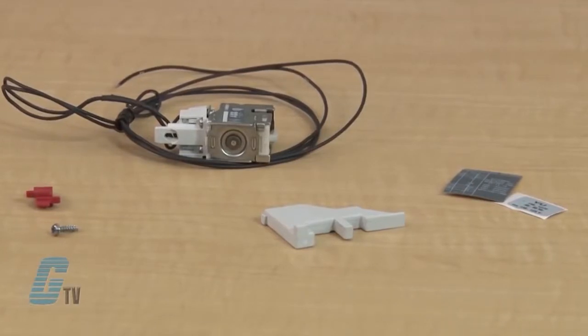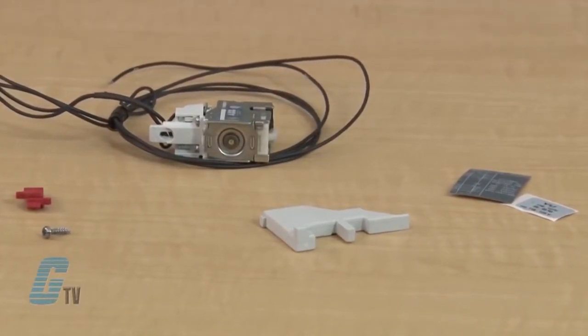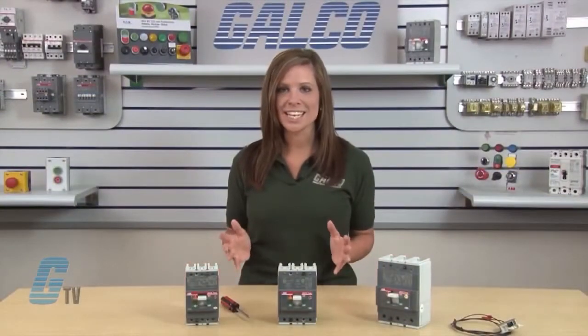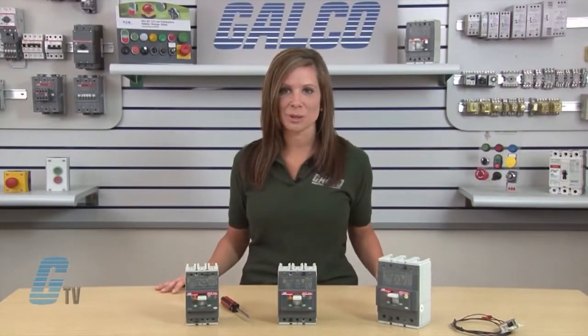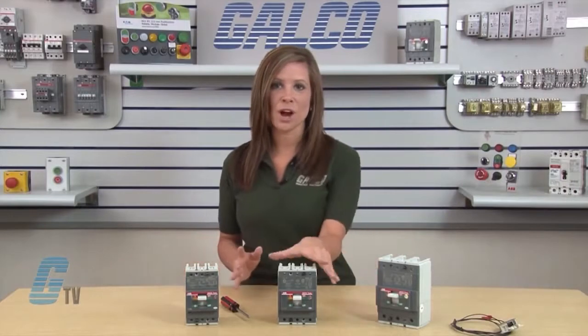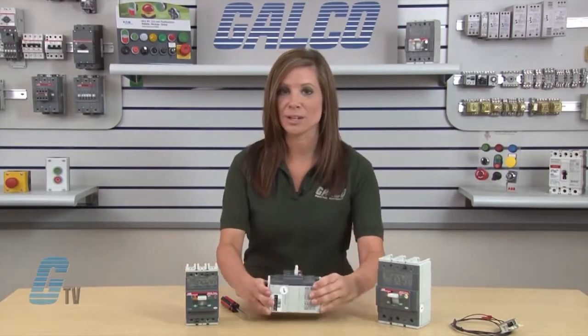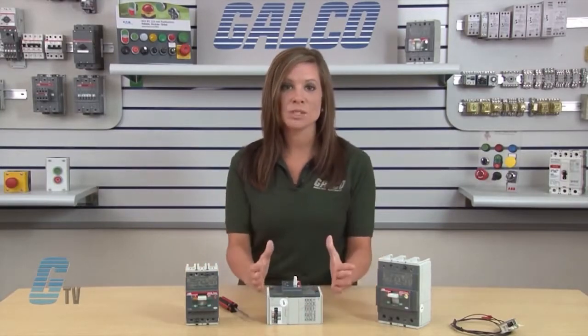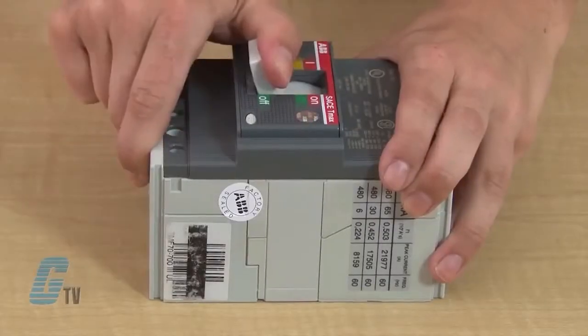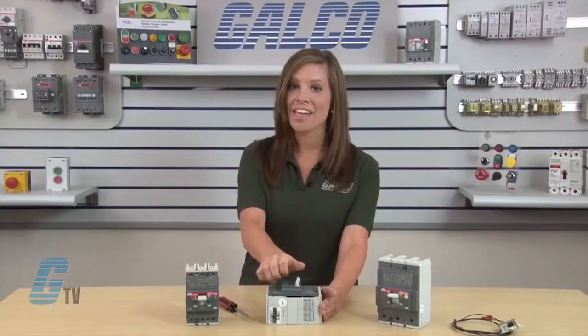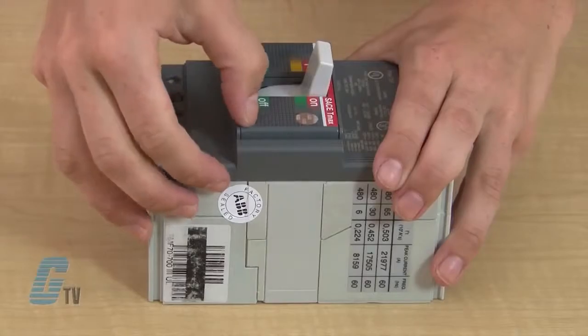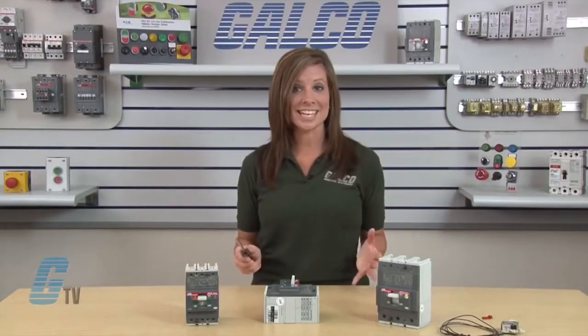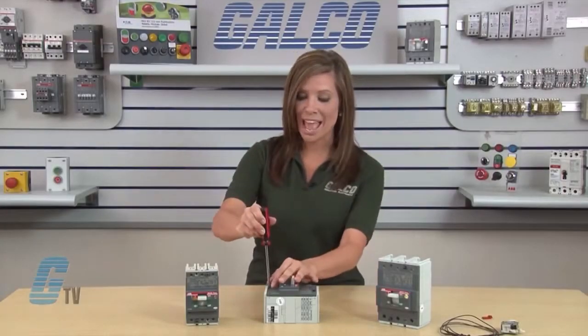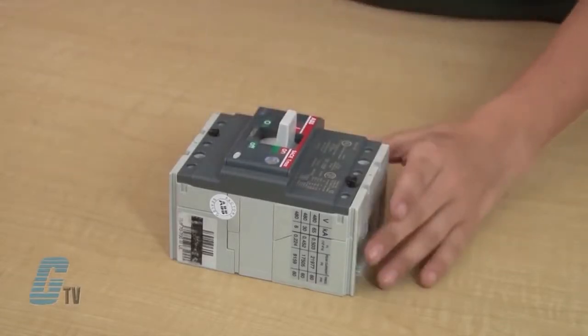This UVR kit includes the UVR unit, a mounting screw, a spacer, an installation tool, and device labels. These are the T1, T2, and T3 circuit breakers. To install the UVR unit, I will need to set the circuit breakers in test position by switching the breaker to off, then on, and then by pushing the test button. Once they are in the test position, I can remove the screws and take off the front plate.